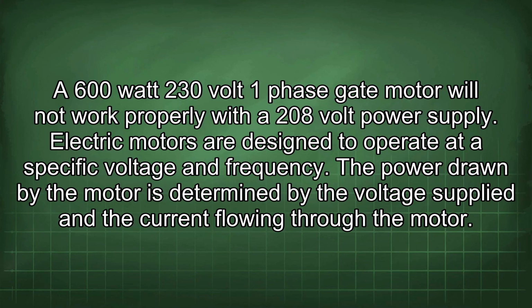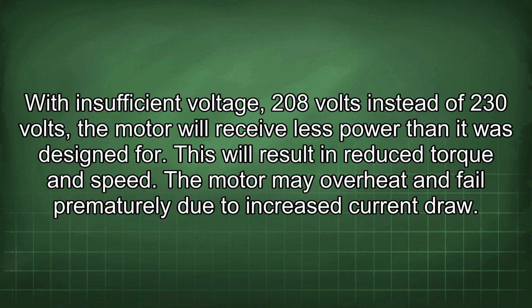A 600-watt 230-volt one-phase gate motor will not work properly with a 208-volt power supply. Electric motors are designed to operate at a specific voltage and frequency. The power drawn by the motor is determined by the voltage supplied and the current flowing through the motor. With insufficient voltage, 208 volts instead of 230 volts, the motor will receive less power than it was designed for. This will result in reduced torque and speed. The motor may overheat and fail prematurely due to increased current draw.